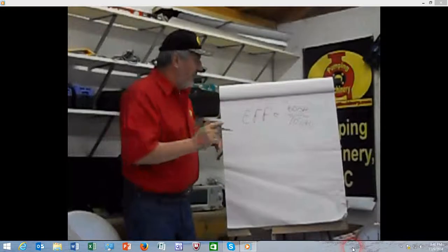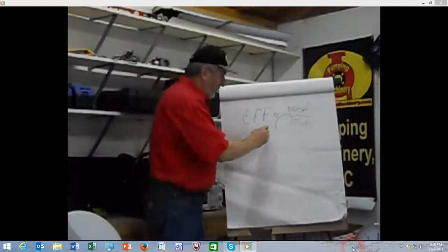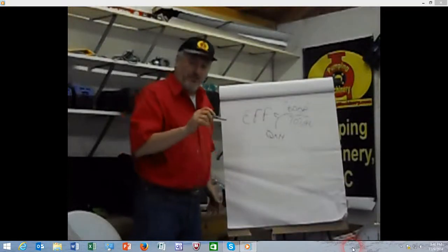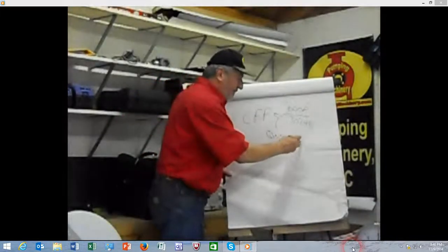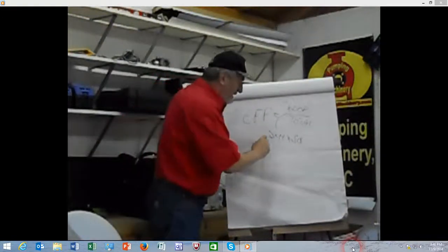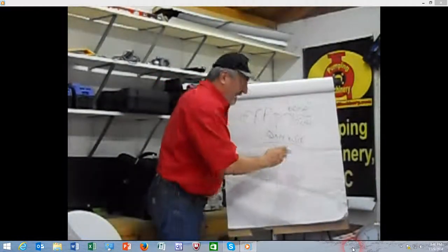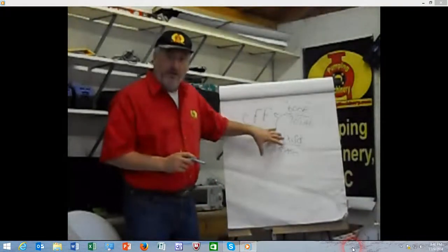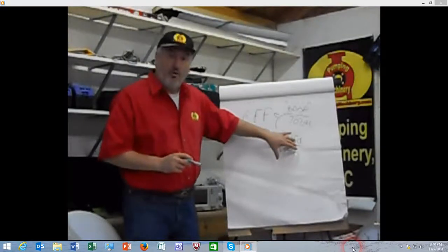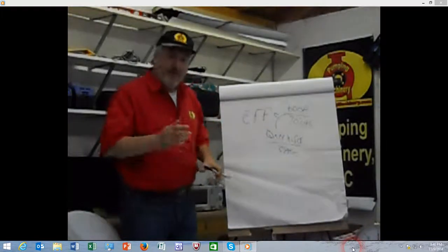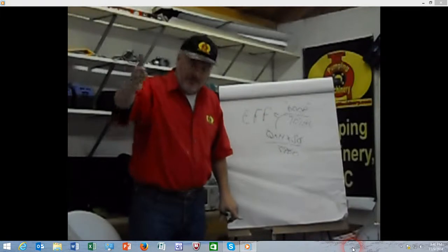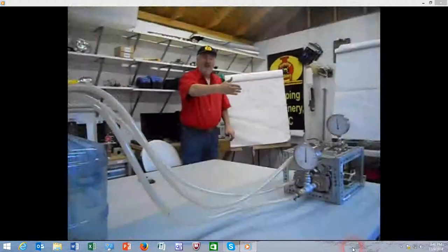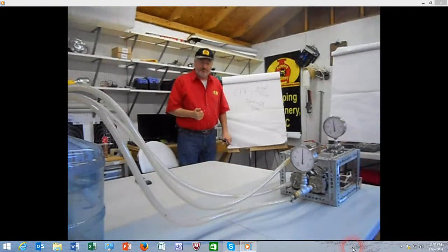The good power, the fluid power, is equal to flow times pump head, as we described in other modules of pump performance, multiplied by specific gravity, and divided by 3960 in the US units. Gallons per minute, feet of head, specific gravity 1.0 in our case, where we have a tank with clean water supplying fluid to the suction of the pump, and then through a flow meter and a set of valves recirculating it back to the tank.